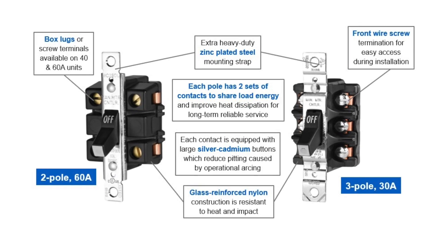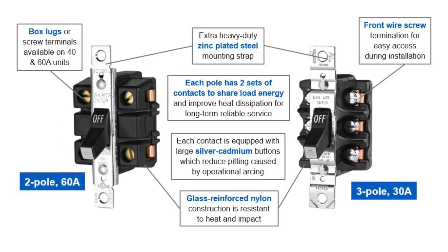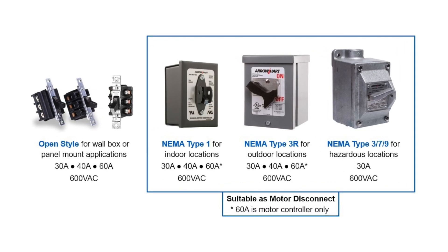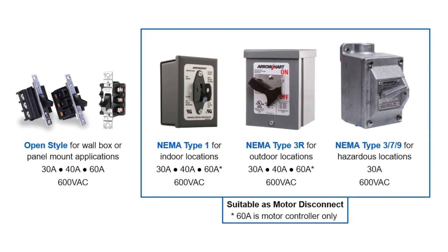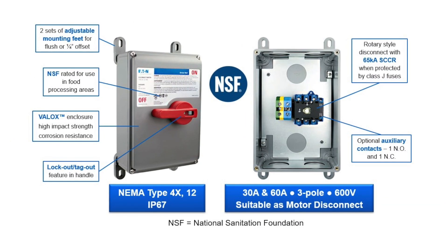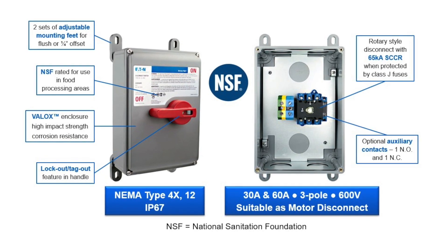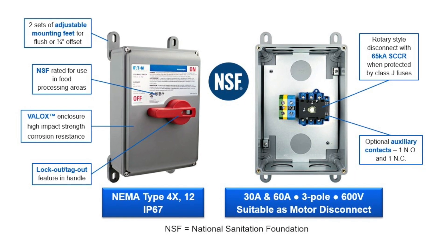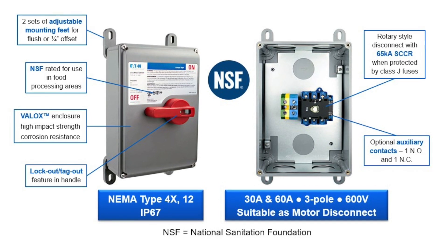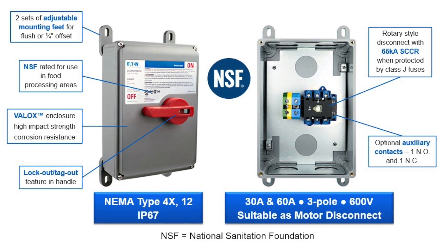Here's a closer look at two of the more common examples. They may be small, but depending on the voltage, they could be used to control up to a 30 horsepower motor. In addition to open style, these toggle controllers come in a variety of enclosures with a lockout/tagout feature that makes the 30 and 40 amp ratings suitable as a motor disconnect. Rotary style disconnects in a VALOX™ enclosure are suitable for both motor control and motor disconnecting means per the NEC and UL 508. These three-pole units are rated 600 volts AC, 30 or 60 amps, and are available with optional auxiliary contacts.